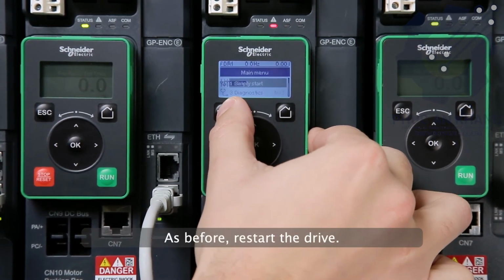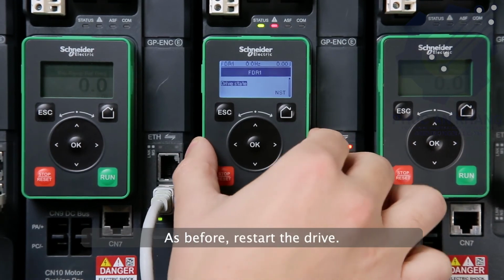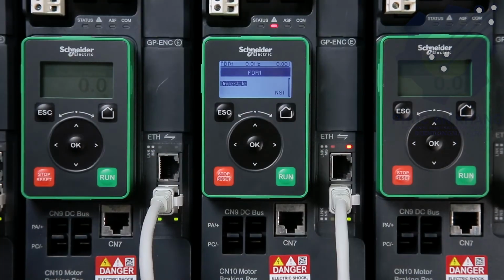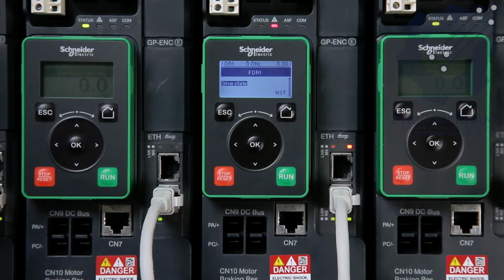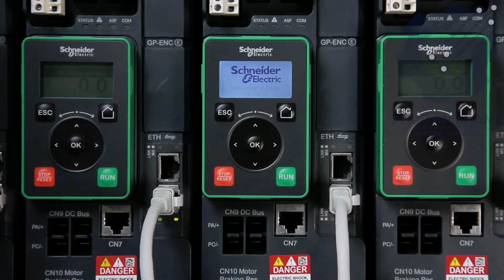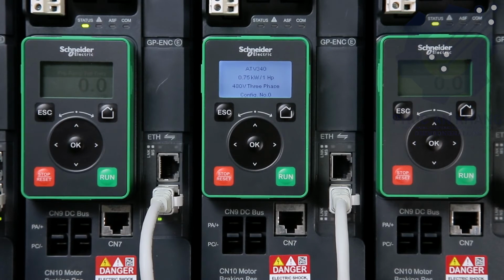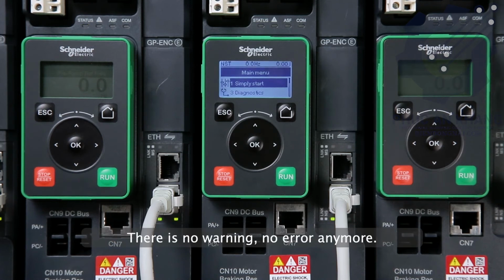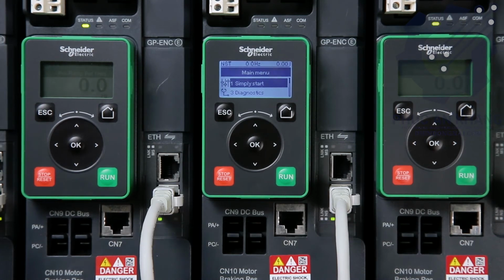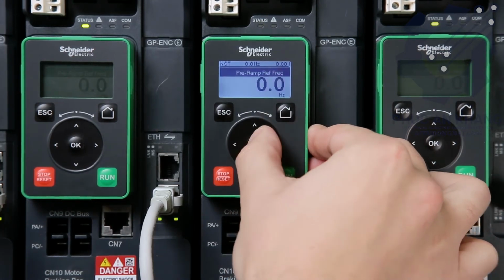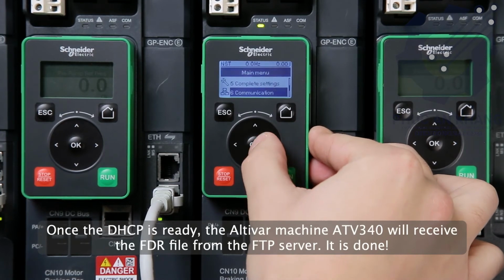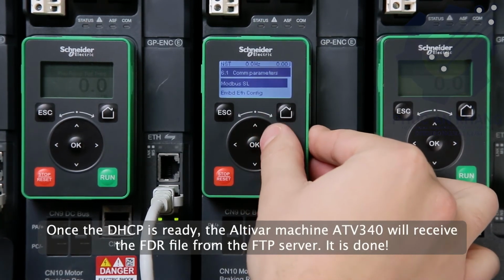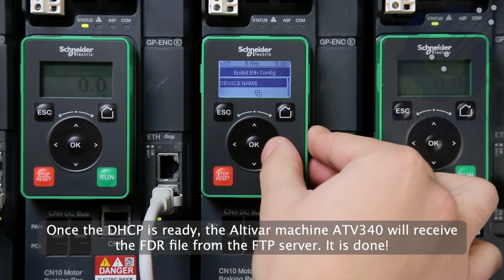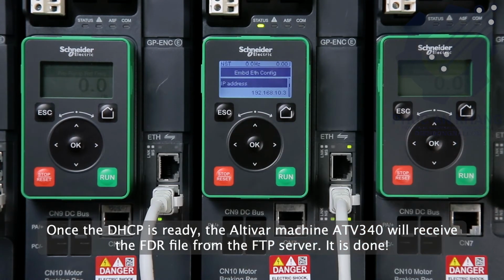As before, restart the drive. There is no warning, no error anymore. Once the DHCP is ready, the Altivar machine ATV340 will receive the FDR file from the FTP server. It is done.